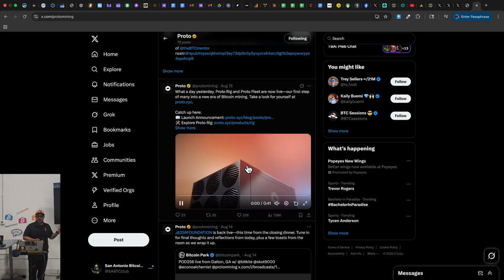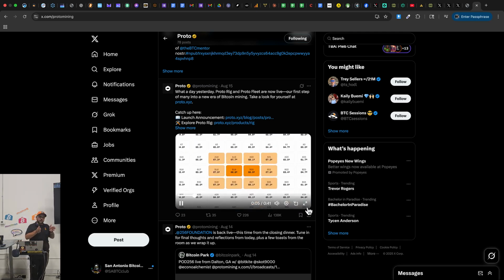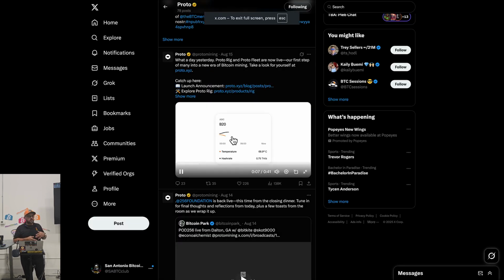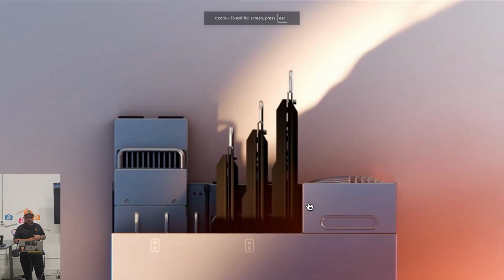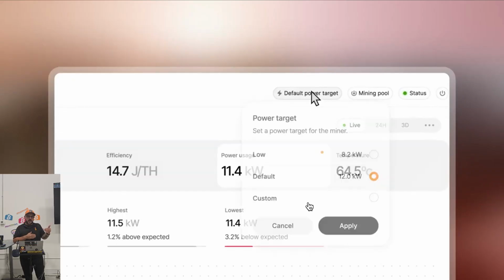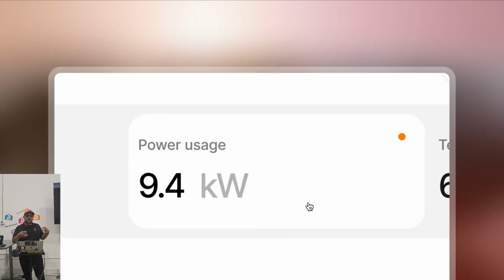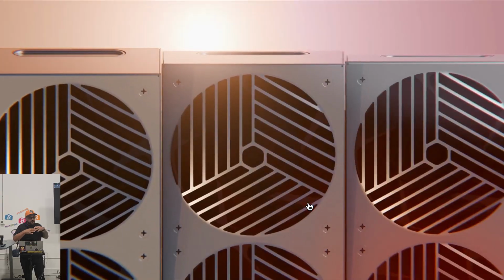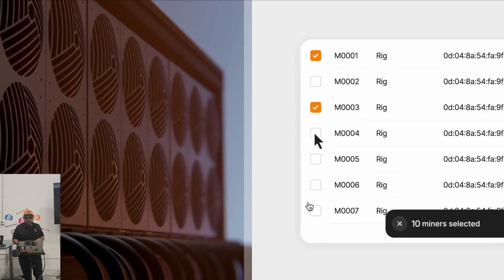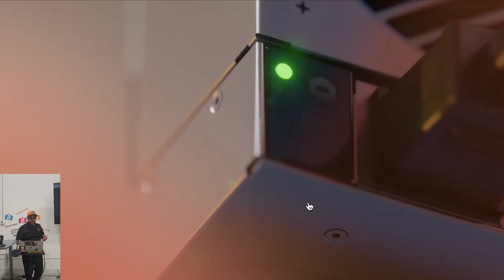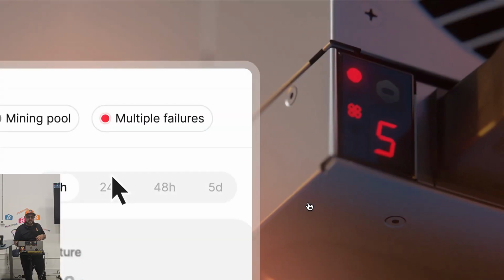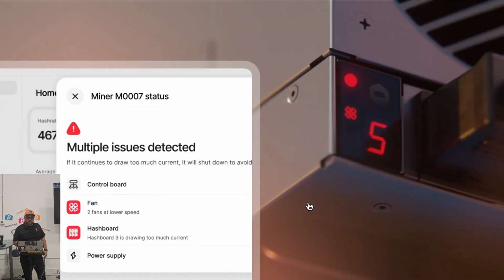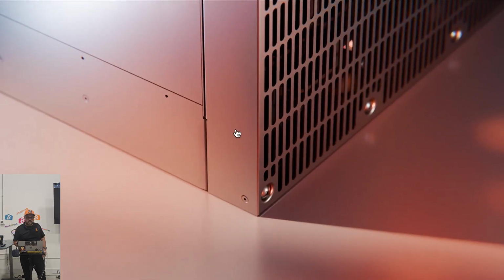And what we hear from a lot of giant operators and fleets and huge mining data centers is that the way they're constructed now, especially a lot of the Antminer S19 series or the S series, they don't fit perfectly, and they're oblong in one area, so it leaves a lot of either cold aisle or hot aisle drafting. And so this being a flush, just basic square, a lot of people that I heard from at this event are really happy about that. It should fit into legacy systems a lot more firmly and get rid of some of those hot and cold aisle issues.